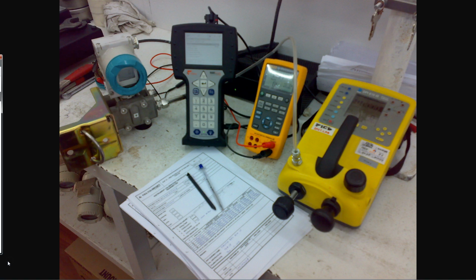Equipment may also require calibration simply because a specified time period has elapsed or a specified usage period has elapsed. Let me go into this in some detail. For some pieces of equipment, there is a 6-month calibration period, which means every 6 months you need to get the instrument recalibrated. With the same principle in mind, some equipment also requires recalibration after a set period of hours. So after 1,000 hours, calibration is required. And in many cases, both options are included. In 6 months or after 1,000 hours, calibration is required.